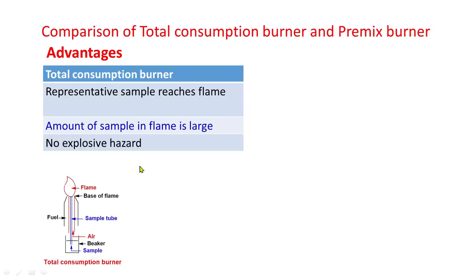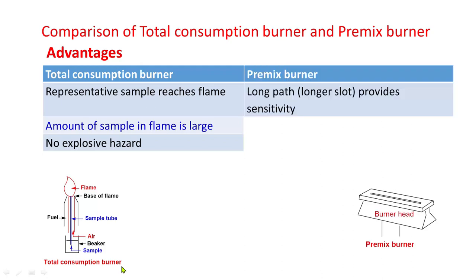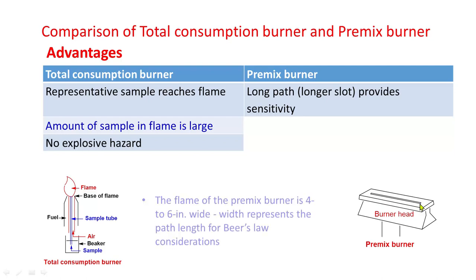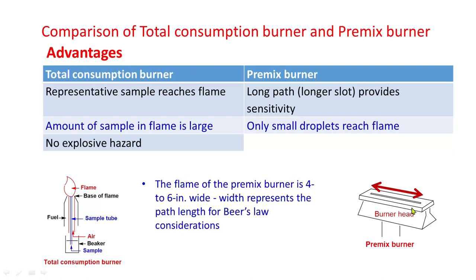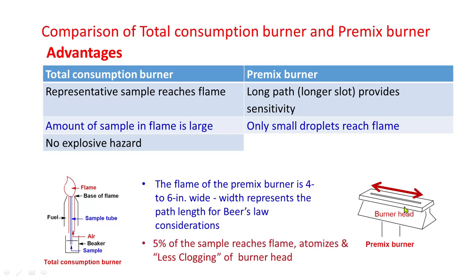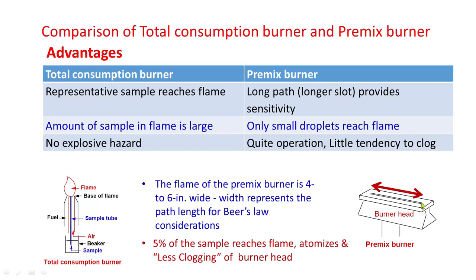Comparing the advantages of the two burners: for the total consumption burner, a representative sample reaches the flame, the amount of sample in the flame is large, and there is no explosion hazard. For the premix burner, the path length is long, providing greater sensitivity. Only small droplets reach the flame, 5% of the sample atomizes, there is less chance of clogging, and it offers quiet operation.